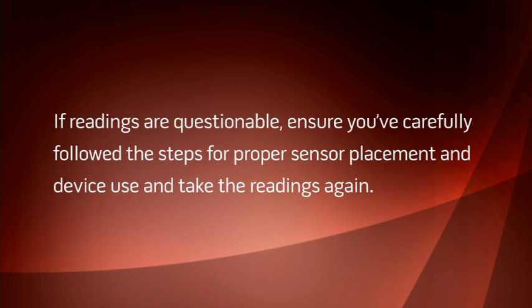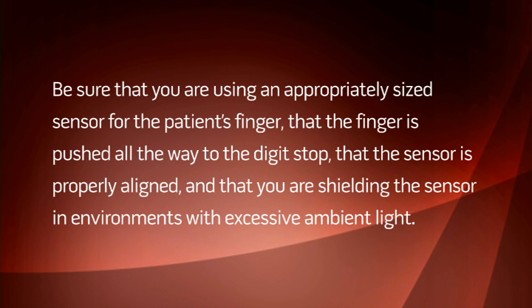If readings are questionable, ensure you've carefully followed the steps for proper sensor placement and device use and take the readings again. Be sure that you are using an appropriately sized sensor for the patient's finger, that the finger is pushed all the way to the digit stop, that the sensor is properly aligned, and that you are shielding the sensor in environments with excessive ambient light. If you have questions about best practices for monitoring SpCO, contact your sales representative and refer to the directions for use for your device and sensor.